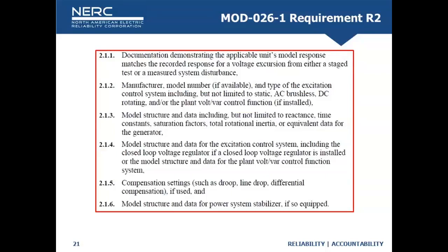And 2.1.1 is really the crucial one - documentation demonstrating that the applicable unit's model response matches the recorded response to a voltage excursion from a staged test or a system disturbance. That one gets a lot of attention, and we heard in Bob's presentation, you do various tests and you see if the simulation matches the test, and if it does, I'm good.